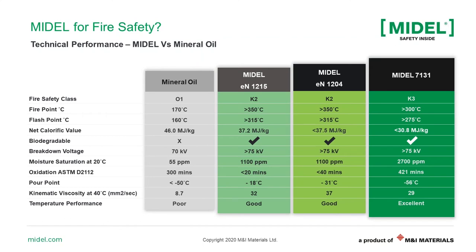Thank you, Steve. Welcome everybody. I'd just like to give you some brief summarising on the fire safety of ester liquids. On this summarising table, you can see many parameters about ester liquids compared to mineral oil. In this webinar, I'd just like to highlight the first four rows from a fire safety point of view. If we see the fire point on the second row, Midel ester liquids have a fire point greater than 300 degrees C, or more than 250 degrees C in the case of natural esters, whereas mineral oil has around 170 degrees C. This is important to classify these liquids as O-class or K-class. The threshold is the fire point: if greater than 300 degrees C, that is K-class; if below, that is O-class.